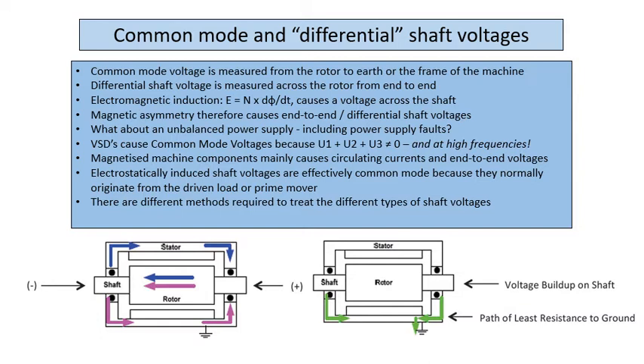The common mode, the way it's caused is, if you look at a motor stator, it is hardly ever grounded. So the voltage that it adopts is equal to your equivalent star point voltage because of the capacitive coupling between the windings. So if you go and measure on a perfectly balanced supply, measure between the frame and neutral, you'll get 0 volts.